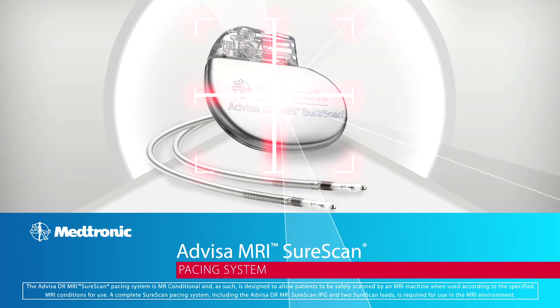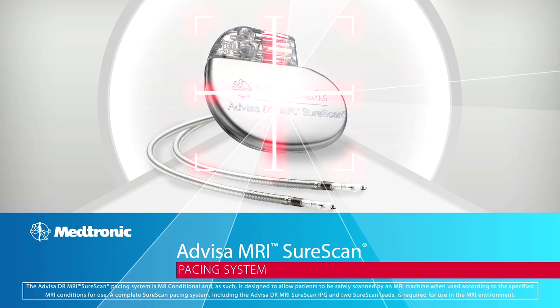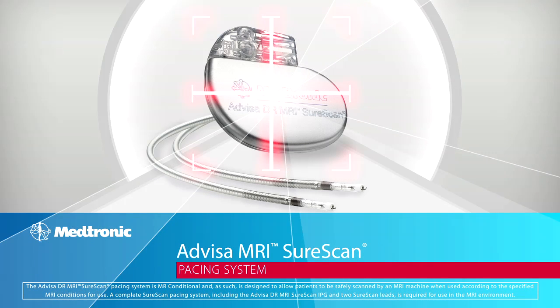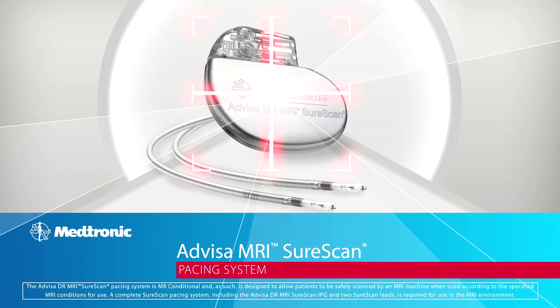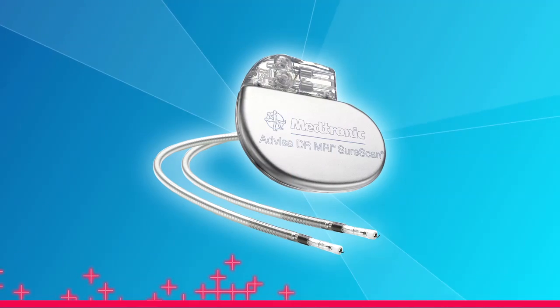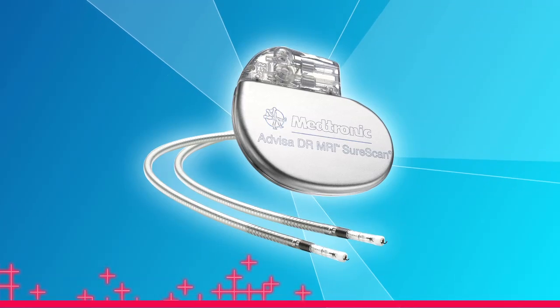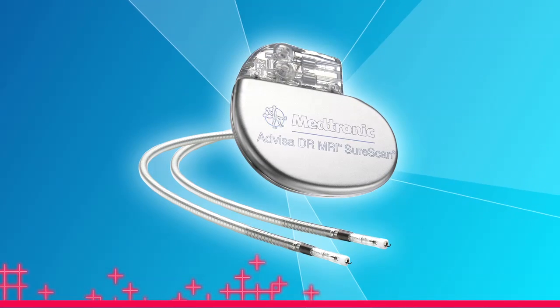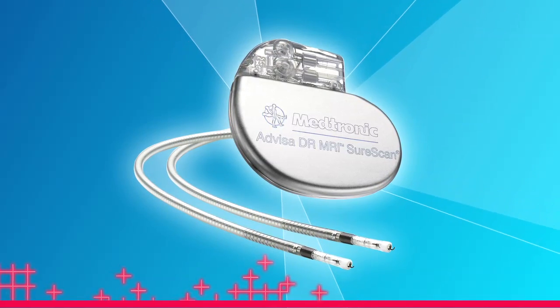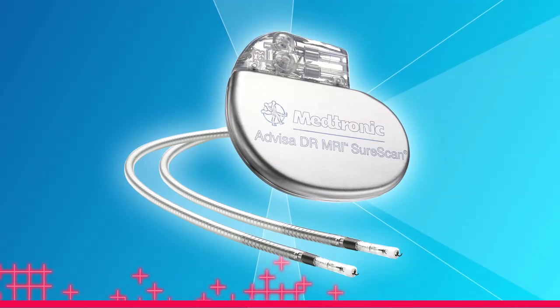The Advisa DR MRI SureScan Pacing System is Medtronic's second-generation SureScan Pacing System, a system approved for use in an MRI environment. A complete system consists of the Advisa DR MRI IPG and two CapSureFix MRI leads. Any other combination may result in a hazard to the patient during an MRI.